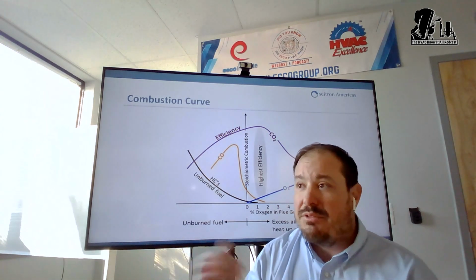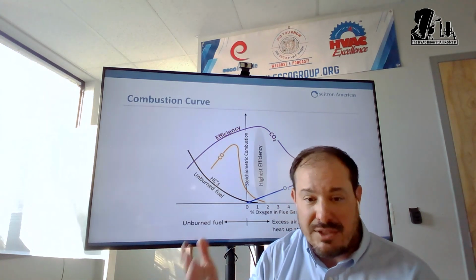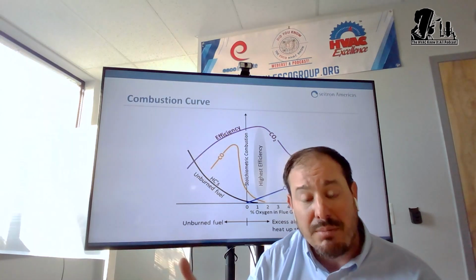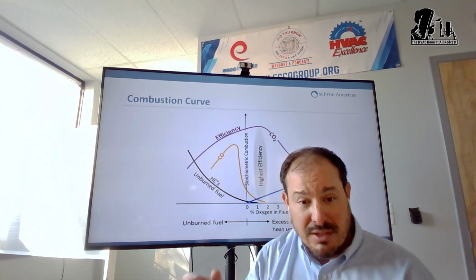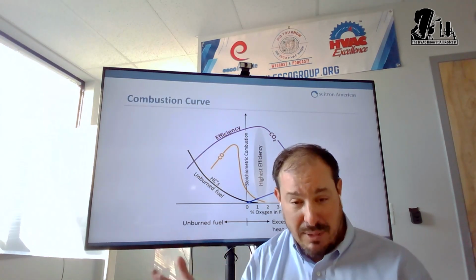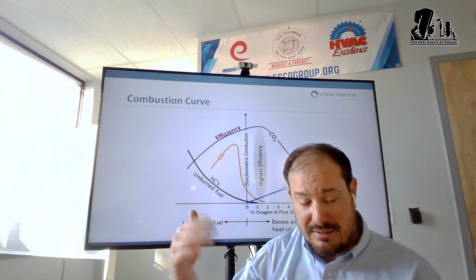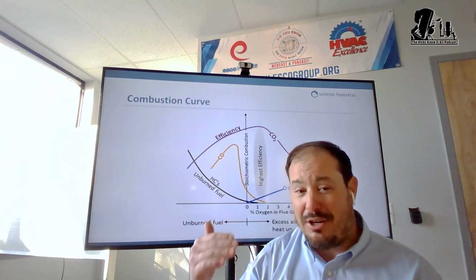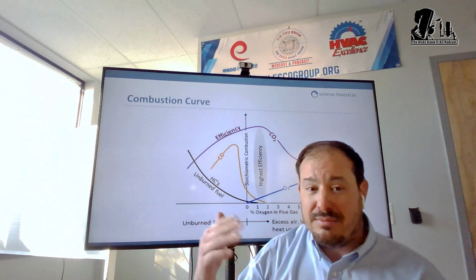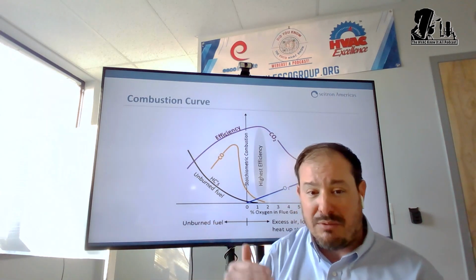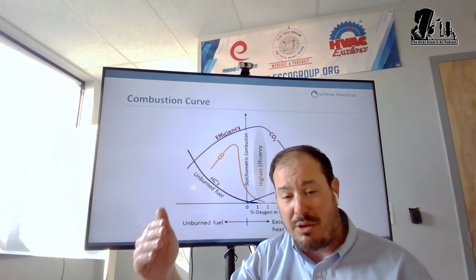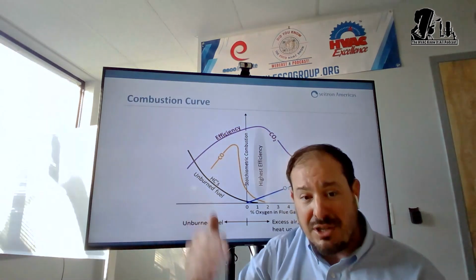The reason why we use excess air is because there are other things in air that could become a problem, like nitrogen, which by the way is about 78% of air. We breathe 78% nitrogen. Well, so does that boiler. At higher temperatures, on the commercial side, you're also going to start increasing NOx. So there's a difference between what residential guys look for and what commercial and industrial guys look for.